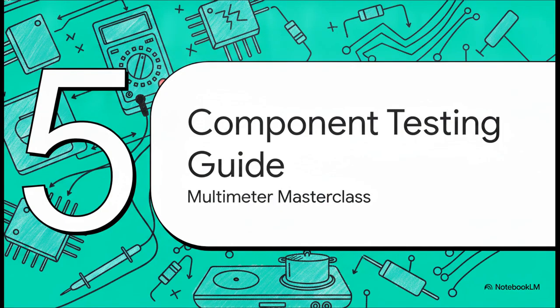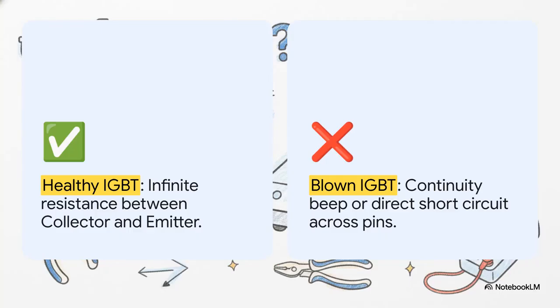Section 5, Component Testing Guide, Multimeter Masterclass. Okay, let's see how this all builds together. We know what components fail, so let's pull out the multimeter and see exactly how to interrogate them at the component level to prove they're dead. Let's start with the heavy muscle, the IGBT, because it is by far the most frequent point of failure. When you remove it from the board and test it, a healthy IGBT will show infinite resistance between the center collector pin and the outer emitter pin. It's essentially an open switch. But with a blown IGBT, your multimeter will let out a loud, continuous beep in continuity mode, showing a dead short circuit across the pins. If it beeps, it's definitively dead. No way around it, it has to be replaced.